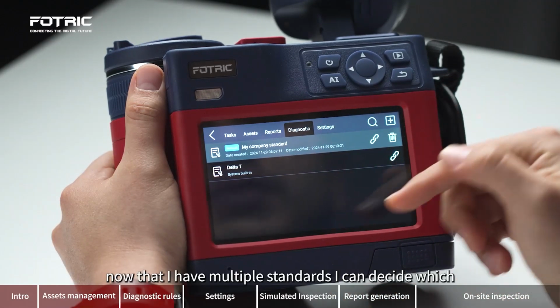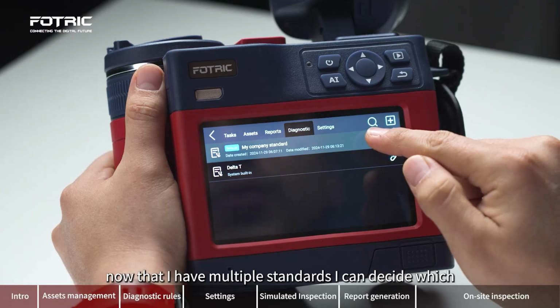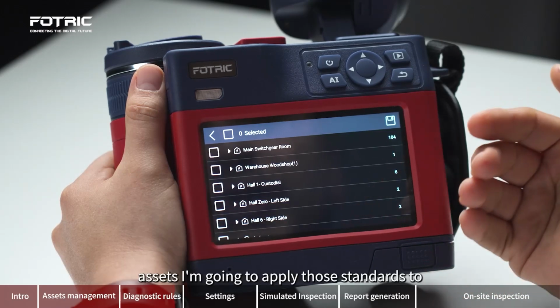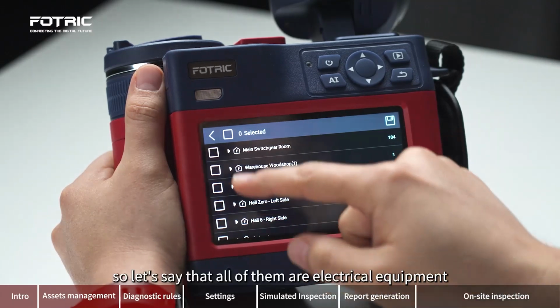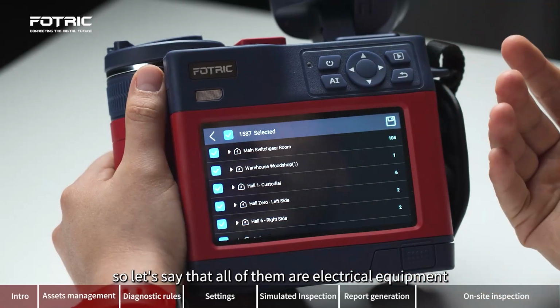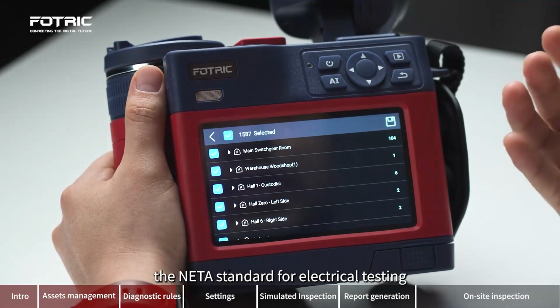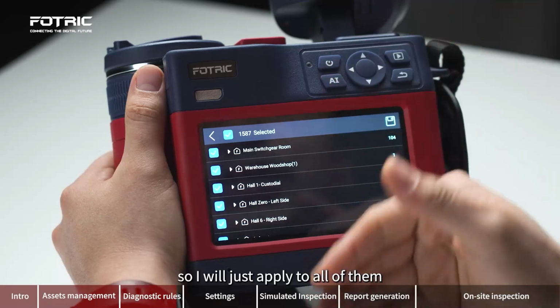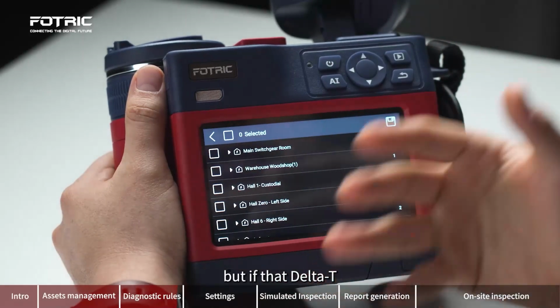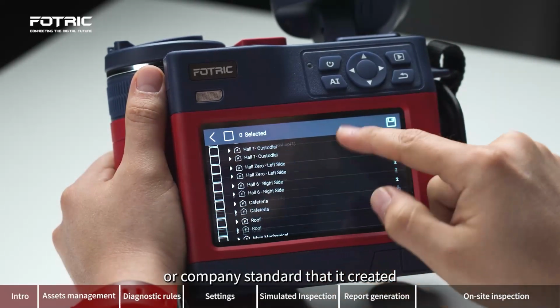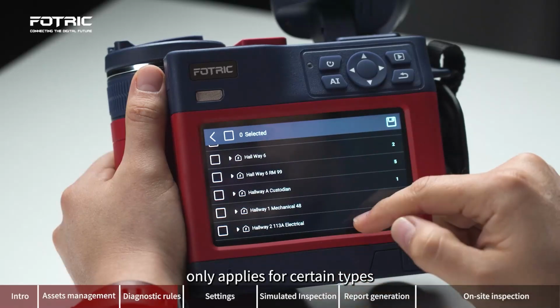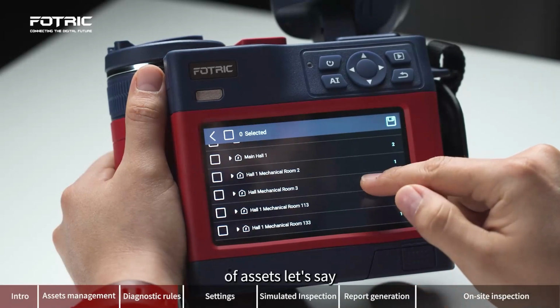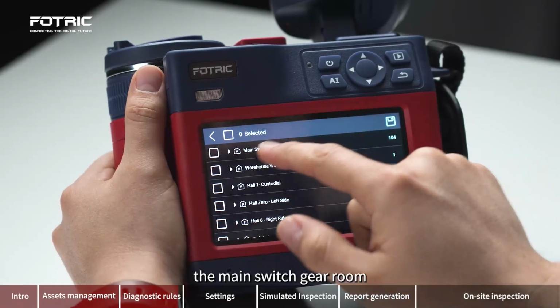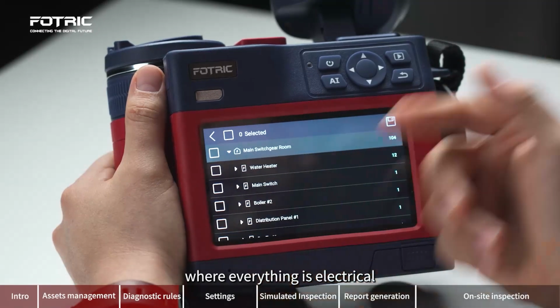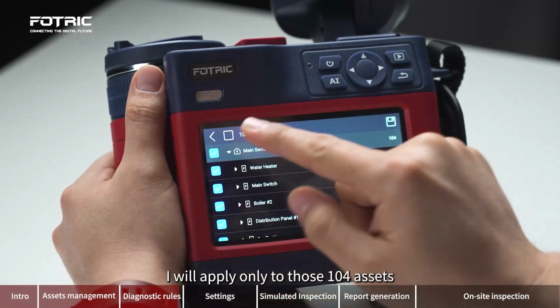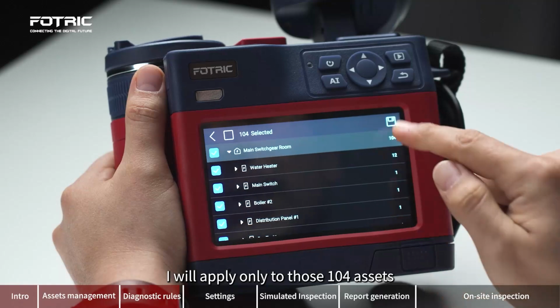Now that I have multiple standards, I can decide which assets I'm going to apply those standards to. So let's say that all of them are electrical equipment and I'm following the NETA standard for electrical testing. So I will just apply to all of them. But if that delta T or company standard that I created only applies for certain types of assets, let's say the main switchgear room where everything is electrical and I'm following that, I will apply only to those 104 assets.